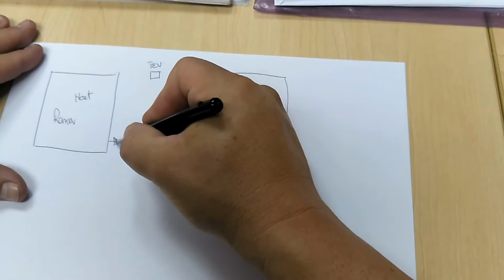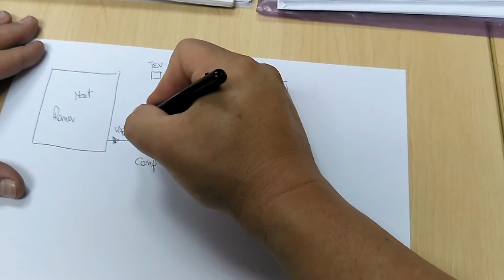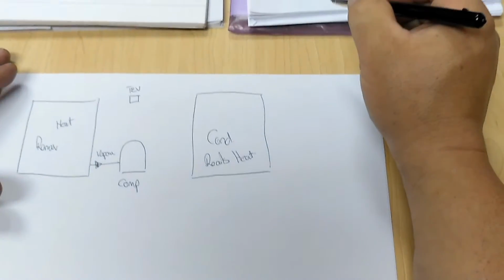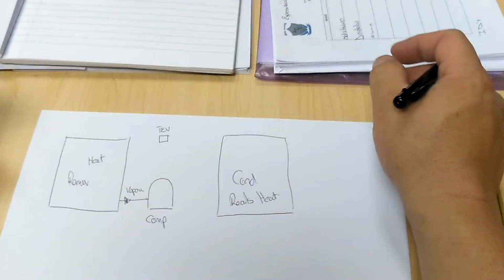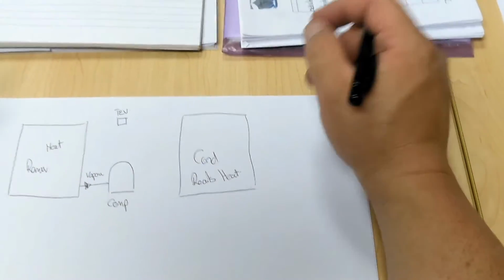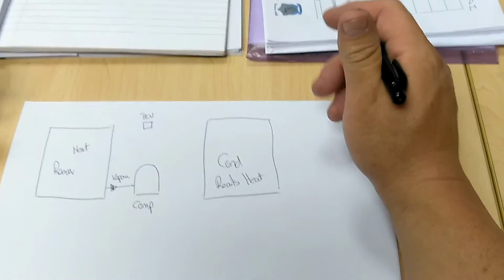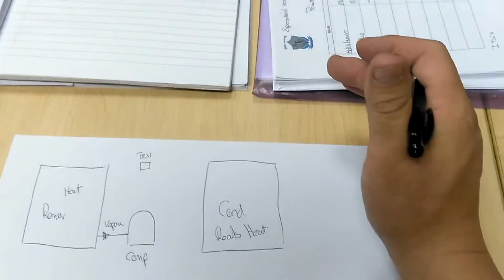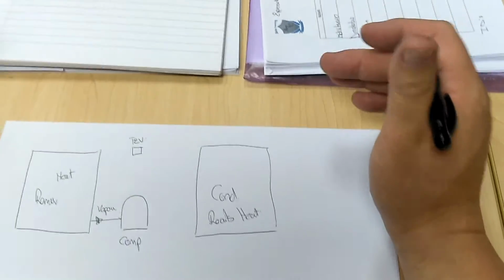From our evaporator, we would have a refrigerant vapor coming in. All right, the arrows indicate the flow. So we have vapor coming into the compressor. As mentioned, and as everybody has seen in previous videos, that vapor entering the compressor is critical. We cannot have any liquid entering the compressor, as this can damage the compressor. A compressor cannot function under a liquid load itself.